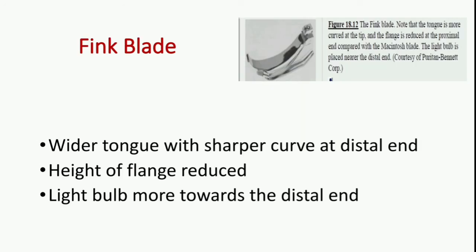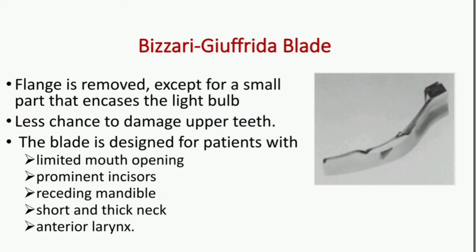The Fink blade has a wider tongue with a sharper curve at the tail end; the height of the flange is reduced and the light bulb is more towards the distal end. The Bizzari Giuffrida blade has the flange removed except for a small part that encompasses the light bulb, so there is less chance of damaging the upper teeth. It is designed for patients with limited mouth opening, prominent incisor teeth, receding mandible, short and thick neck, or an anterior larynx.